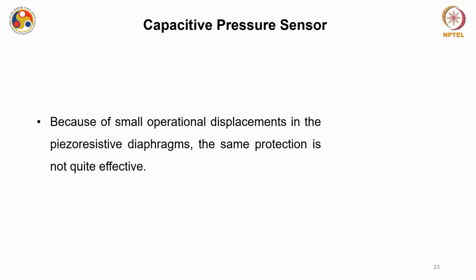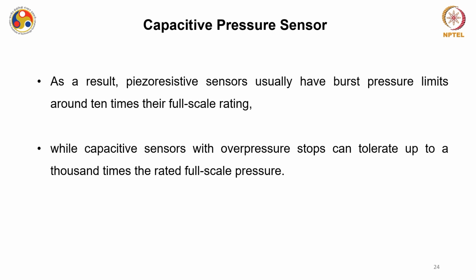differential pressure sensor. Because of small operational displacements in the piezoresistive diaphragm, the same protection is not quite effective. As a result, piezoresistive sensors usually have very low burst pressure limits, not more than 10 times their full scale rating. However, for a capacitive pressure sensor, when you place these overpressure stops, it can tolerate up to say 1000 times the rated full scale pressure.